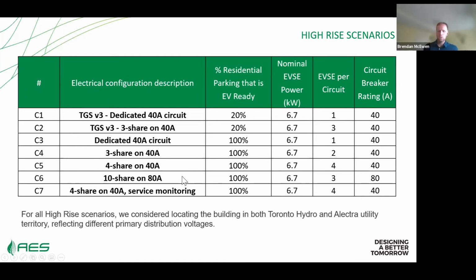There are relatively few EV charging service providers out there right now who can implement charging on 80 amp circuits for these 6.7 kilowatt EVSE. Right now the electrical code says you need EVSE that match the power of the branch circuit - I think there's a good chance that'll change, since it's not frankly a sensible requirement. There are also EV charging services with an internal circuit breaker in the EVSE that allows for this, so we see this becoming increasingly viable in the future.